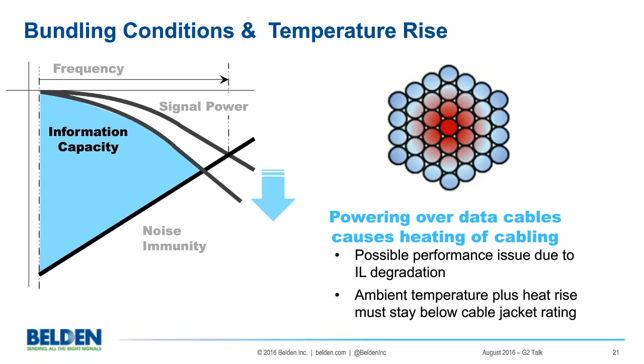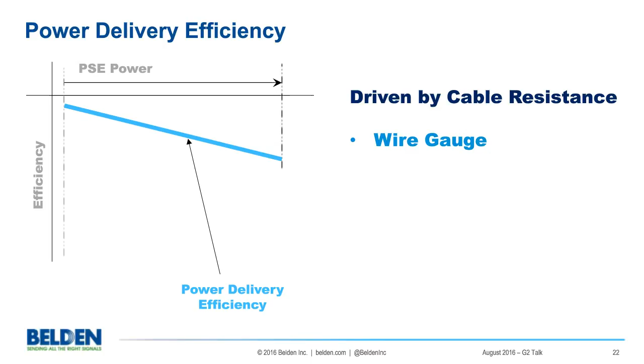Now let's look at the new metric, power delivery efficiency. What is it? Simply put, it is a function of the DC resistance of the cabling. What governs this DC resistance? One thing is wire gauge. Wire gauge is the diameter of the conductor wires in the cable itself. What is the relationship? As the wire diameter goes up, the DC resistance goes down. Another factor that can govern DC cable resistance is the temperature. The relationship is, as the temperature goes up, the DC resistance also goes up.